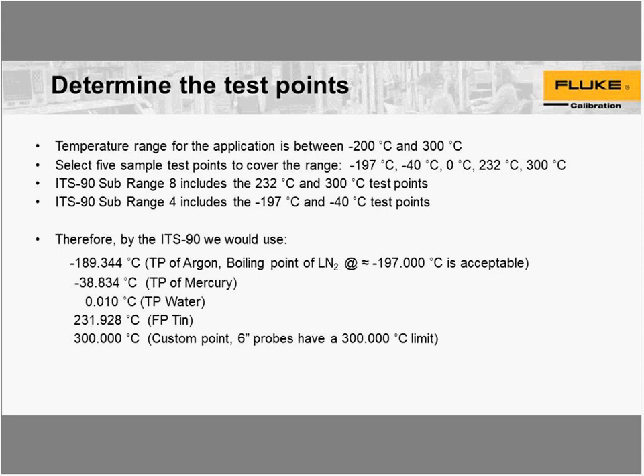The ITS-90 subrange 8 will have the 232 and 300 degree test points, and subrange 4 will include the minus 197 and minus 40 degree test points. So by ITS-90, we would use minus 189.344, which is the triple point of argon, or the boiling point of LN2, liquid nitrogen, is approximately minus 197 and is an acceptable substitute. Okay, not everybody has a triple point of argon that they can actually use. They're rather expensive, and at this point it's still hard to come by.